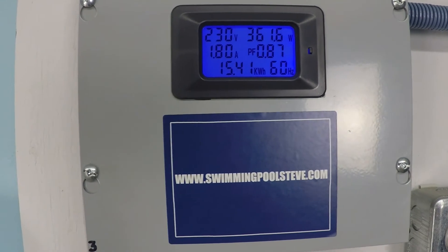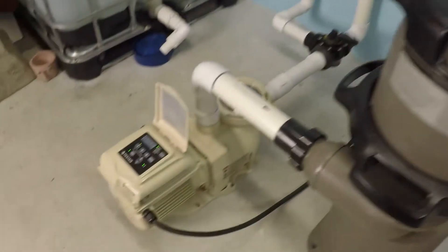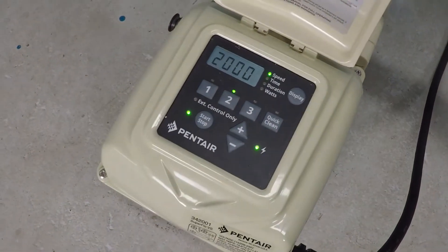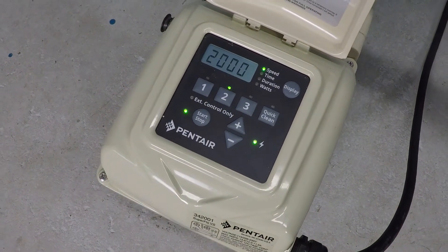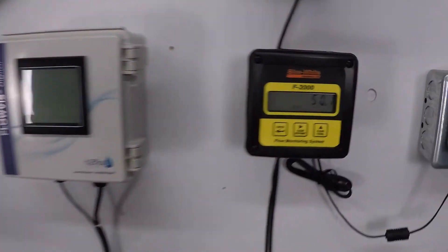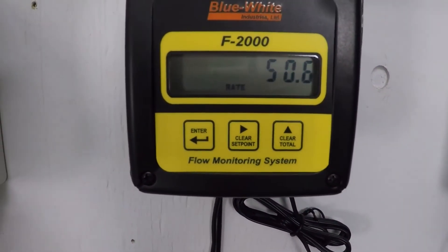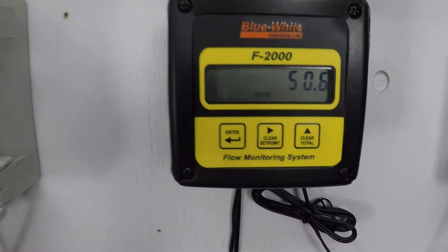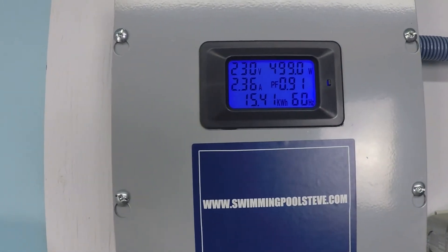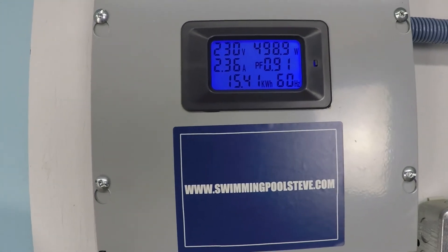Power has increased to 366 watts at the next increment. We're now at 50.8 gallons per minute, just under 500 watts, and 2.36 amps of current draw.